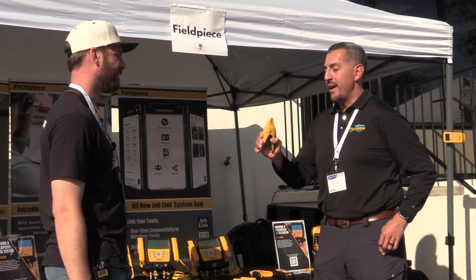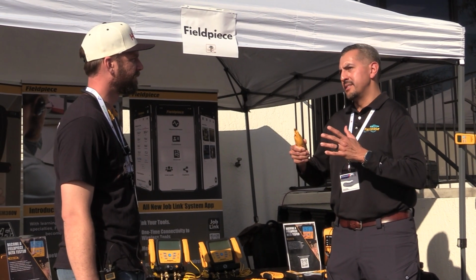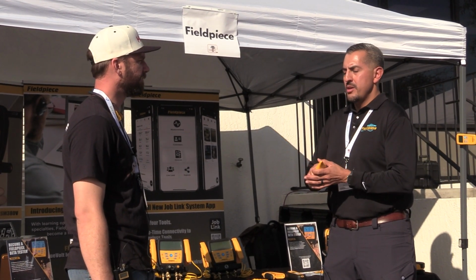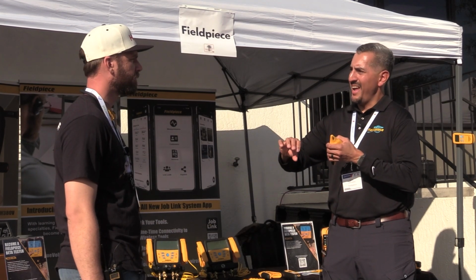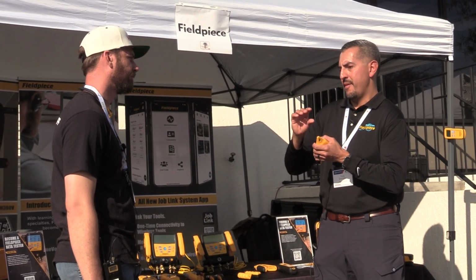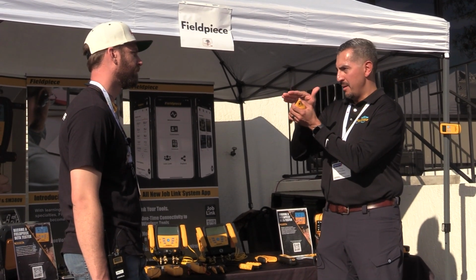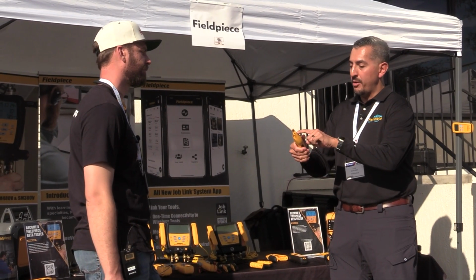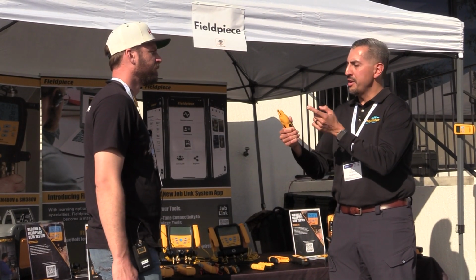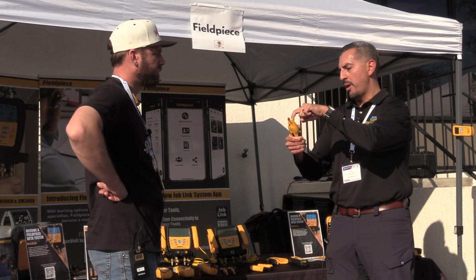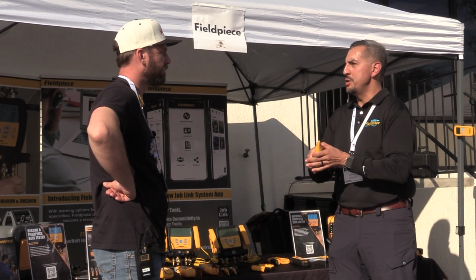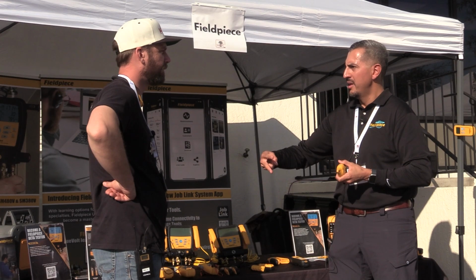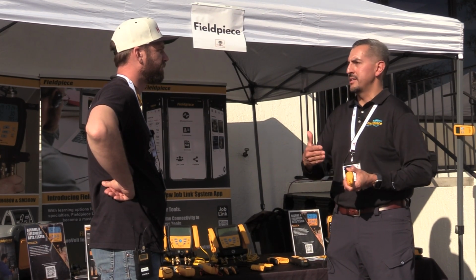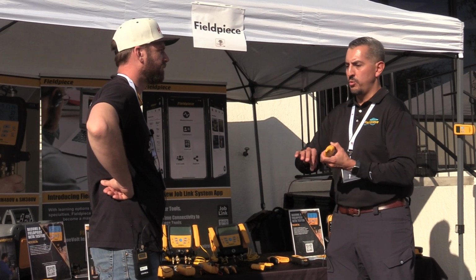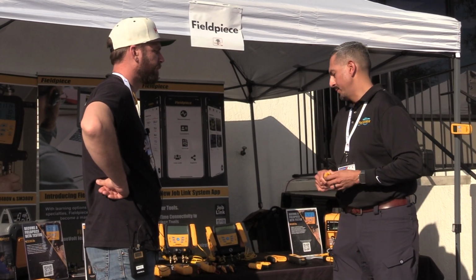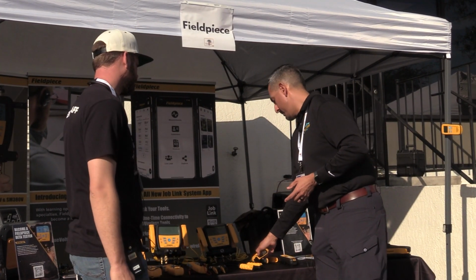The other benefit of this type of technology is with your traditional pipe clamp, you really have to put it on a flat section of the pipe because you want as much of the pipe touching that metal plate. Whereas with RapidRail, you aren't limited to that—all you need is a single point of contact anywhere on the strip, meaning you can put it on an elbow if you had to, and still get the same accurate reading as you would on a flat run of pipe. So I love it.